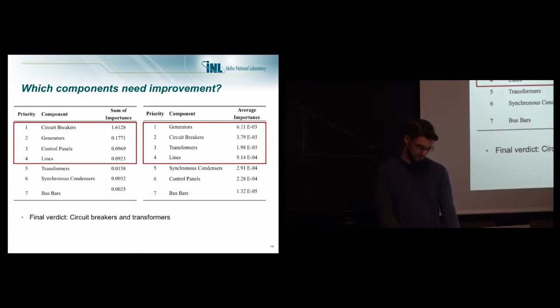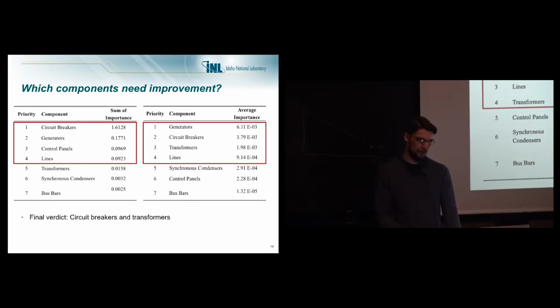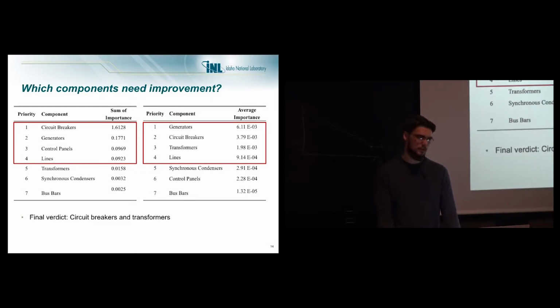If you take a look at the top grouping of 4, we have circuit breakers, generators, lines, and transformers. If you look at the sum, it's circuit breakers, generators, lines, control panels are in there too, but 5th is transformers. And if you look at the average, it's generators, circuit breakers, transformers, lines. So ultimately, it's going to be one of those 4.